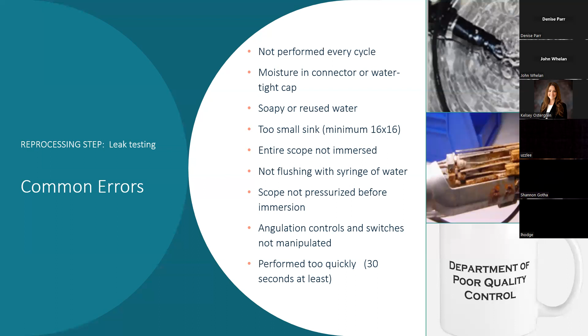What you see on the screen are some common leak testing errors, including simply not performing this every cycle. For example, if a scope is overcoiled, if it's coiled too tightly, using a sink that's too small, leaks may not be discovered. We often see scopes not completely immersed in water or immersed in water that already has detergent added to it. So it's not uncommon to see staff going too fast or not taking the time that's prescribed to perform leak testing.